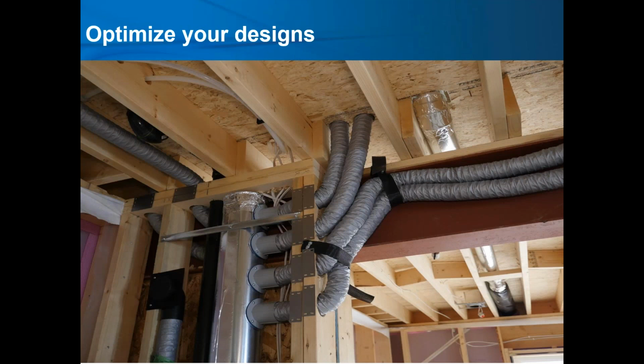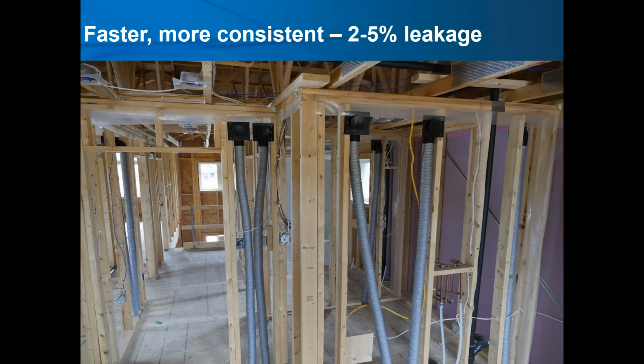Let's talk about optimizing your design. So again, off of 6-inch or 8-inch mains, 2.5-inch flex ducts, we're able to get nice clean installs, and we've got guys using TJI. They're just pre-cutting holes through the boards, and the HVAC guys can just come in and feed through quite easily and simply. There's also debris caps all the way through, so no chance of getting dust and debris in those ducts during install. And more importantly, we're getting 2 to 5% leakage and a much faster install and more consistent install.